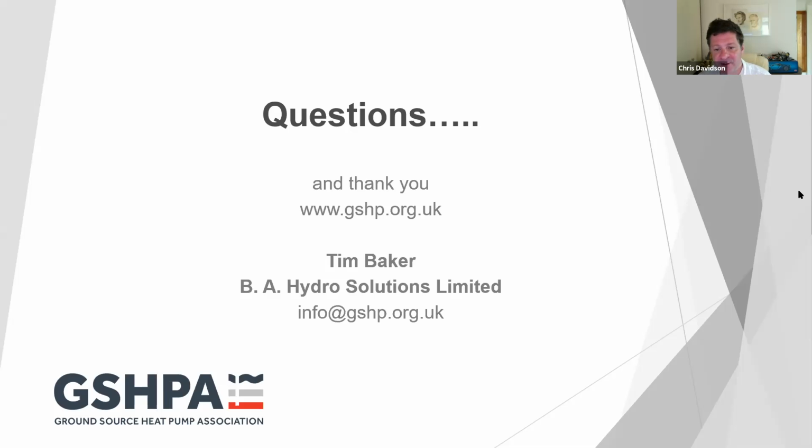Yes. Okay, so a quick question from Peter McAvoy. When we're talking about modelling, do you mean something like EED, Earth Energy Designer, or something else like taking vertical thermal complexity into account? I think it's the former, the software packages, Tim. It is, yeah. It's typically EED or GLD or software along those lines, so you can take the thermal values out and adjust them. As you go through your design process, you might start with, well, let's aim to do holes to 150, but if through modelling you arrive at 120, then you just rejig your thermal values so you get a representative value for ground level to 120, etc.